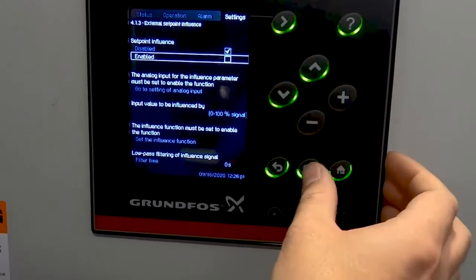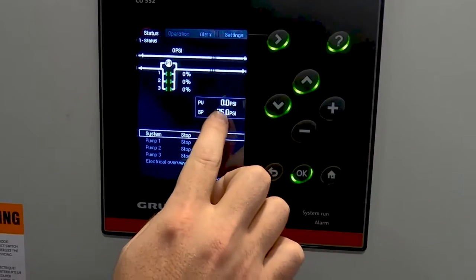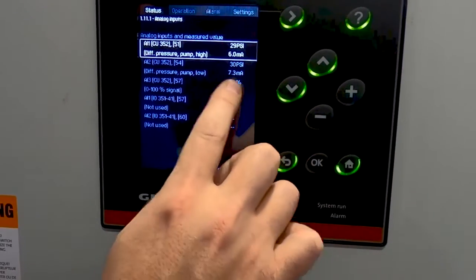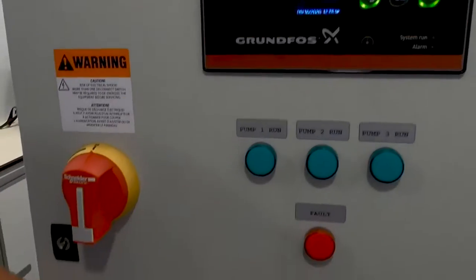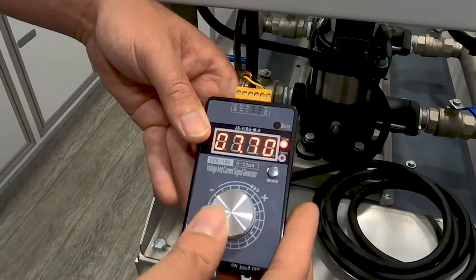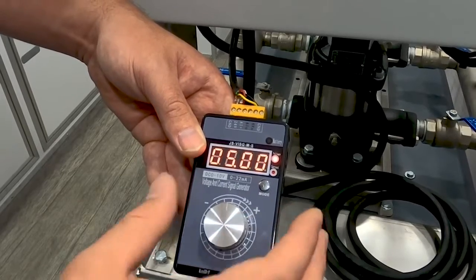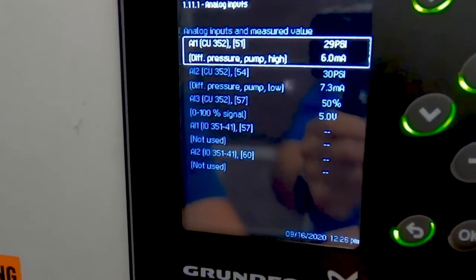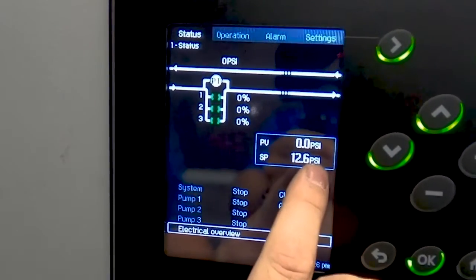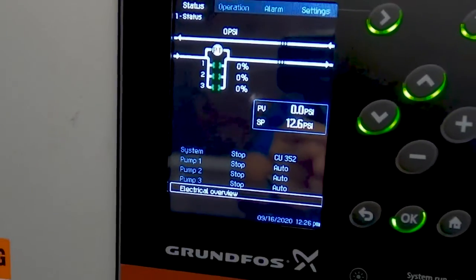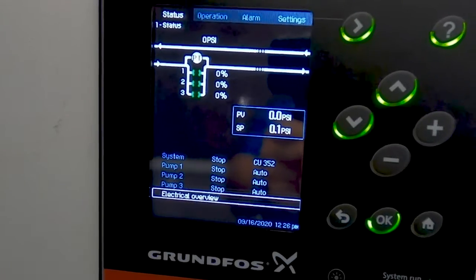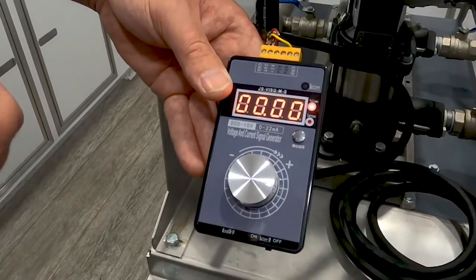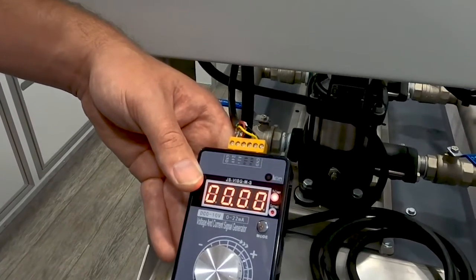Now that this is set up, I'm going to enable this function. From the home screen, you can see the set point is 25 psi. If I go to electrical overview, analog inputs, I'm at 100%, which is 10 volts. Now if I change this back down to five volts, you can see on analog input three I'm now showing five volts and 50% of the set point. Going back to the home screen, that 25 psi has now been cut in half. And if I follow that down further to zero, you can see this goes down to close to zero set point. This may be required depending on if the engineer wants to send a four to 20 or zero to 10 input to influence a set point.